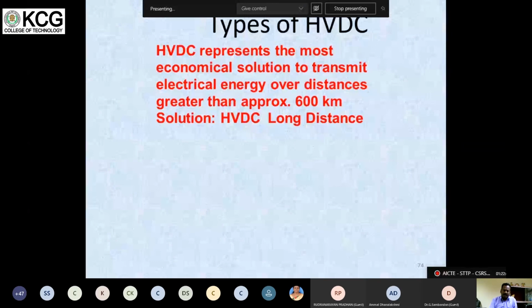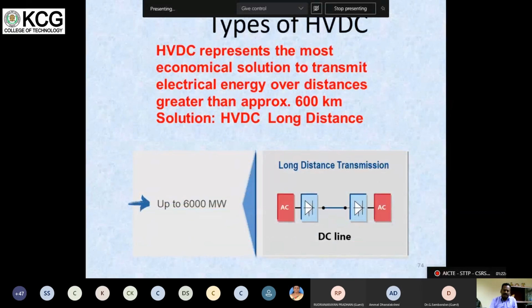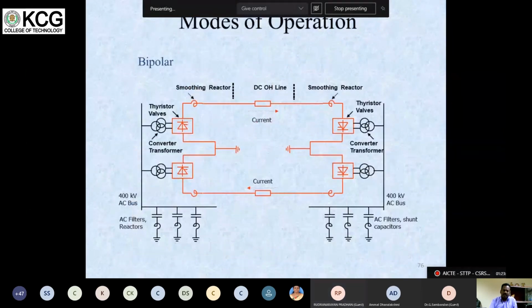Then another we have is the long transmission system, or bipolar system. In India we have a maximum capacity of 6,000 megawatt. So 6,000 megawatt of power is transferred through a single transmission tower. That is the advantage of the HVDC transmission system in the grid. In the long distance system, at the sending or generating end, power is converted to DC, and the DC power is transmitted over a longer distance, and at the receiving end the DC power is converted to AC power. This is the mode of operation. In this bipolar system, both plus and minus poles are operating.